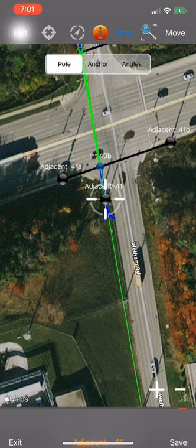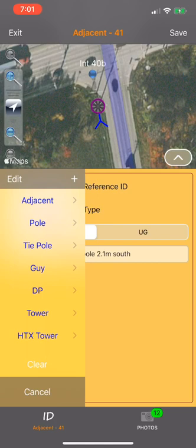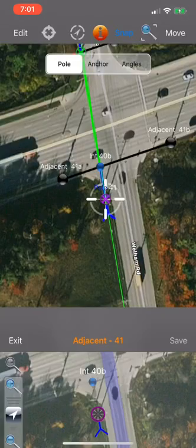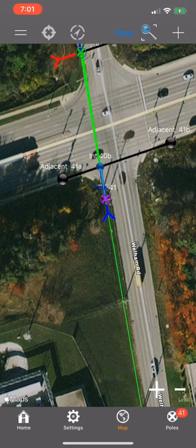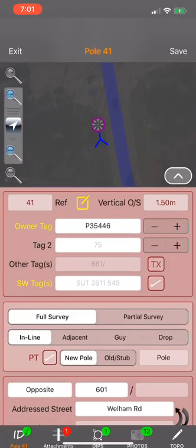The maximum amount of poles you can have in a project is 124, because the CAD outputs will not allow you to do more than 250 odd tab views, and you need a cover page, so 124 is the max.